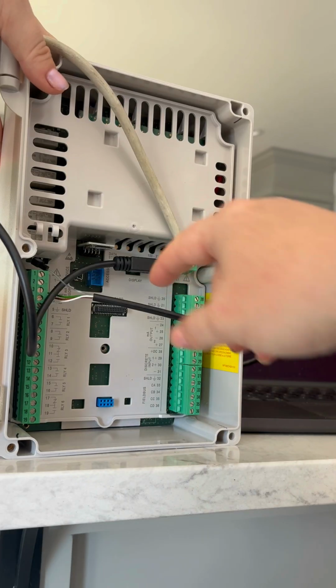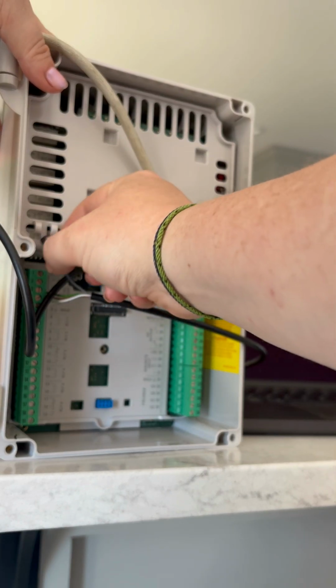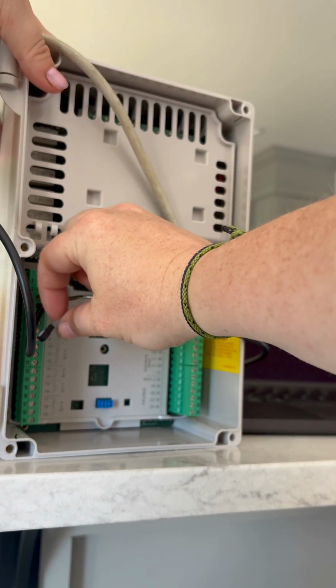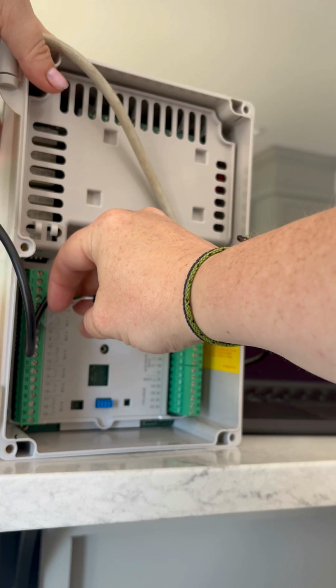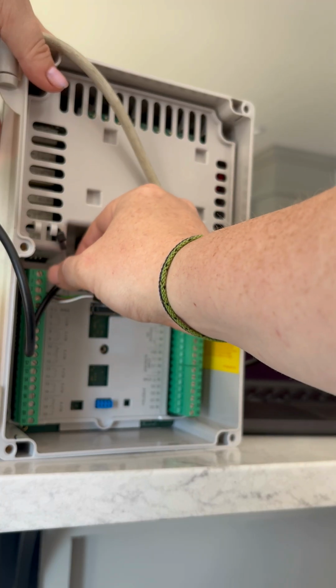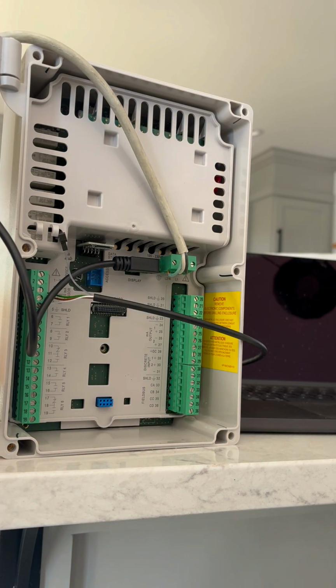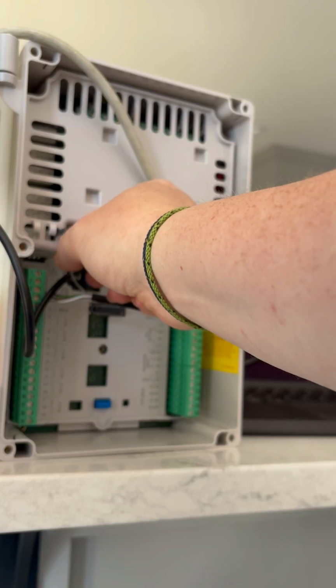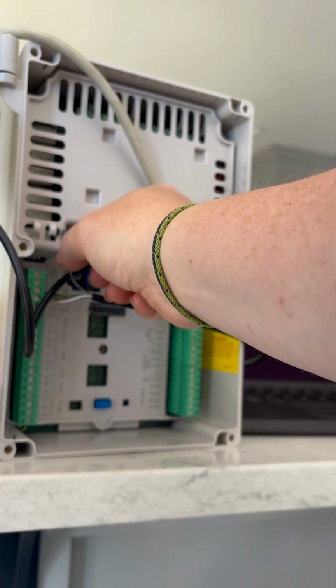I do want to note that I have it wired up currently. You can see here that the hydrostatic has this venting tube. This is why we don't want to wire directly into the controller for a long-term application. Just for setup and commissioning is no problem, but we want to make sure the cable goes into the junction box that comes with the LH100 so that it's vented properly.